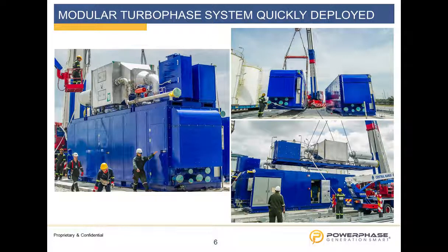All right, the outside of the box. As mentioned, it's a modular system. What you see here is an install in Southeast Asia that was recently completed. The purpose of these pictures is to show you the box is delivered in 2 lifts. It's fully assembled and fully factory acceptance tested. When it's delivered, it's the major kit that you see on the top right, and then a roof skid that's lowered onto the roof. It has 6 connections, and the 2 units in this picture were put together in a day. Prior to arrival, you pour the civil concrete works and run the pipe connections for the fuel, air, and water. Assuming all those are done in advance of arrival, the box itself is delivered and put in place in a day.